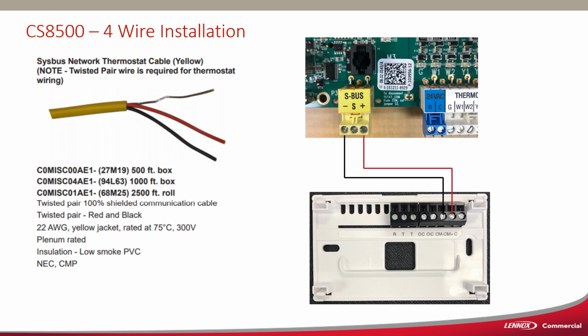You can see our part numbers there. You can order this wire from us, and it's made for us by Belden. As long as it meets the specifications, 22 gauge, twisted pair, shielded cable with ground, you should be fine. For the 24 volt supply on this, you can use thermostat wire. In fact, that's my preference. I don't want to see the voltage line, the 24 volts, inside of the conductor. So even if you buy this wire with 4 conductors, we don't want voltage, whether it's line voltage or 24 volts, inside the jacket of the control wire.